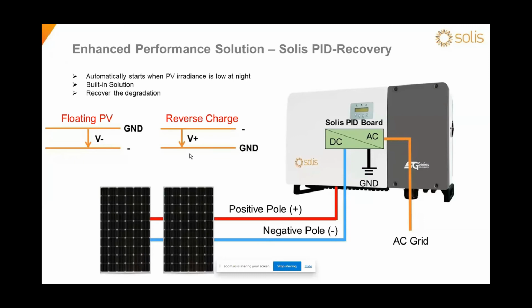Our solution to protect the PV panel from PID is to apply a reverse voltage on the cell, which cancels out the PID voltage so the cell can be protected. There's a special PID board inside the inverter, and it adds that reverse voltage at night when PV irradiance is low.